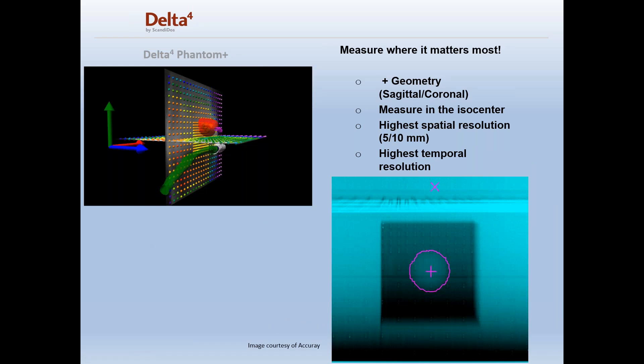The diodes are positioned internal to the phantom on a sagittal and a coronal plane. The measurement is at isocenter in most cases, depending upon how you position the phantom. At the center 10x10 region there are 5mm spacing, and outside of that 10x10 region there are 10mm spacing.